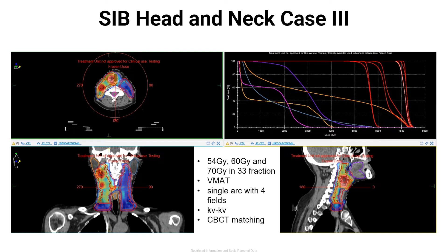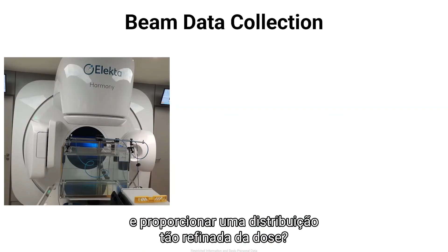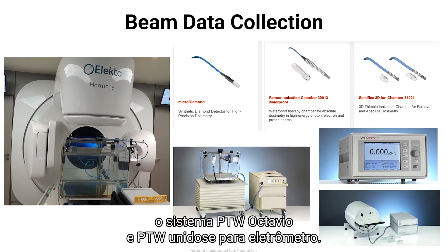So finally, let me give you the technical evaluation of the machine, and how this system can treat patients very successfully and give you a very elegant dose distribution. First of all, it starts with beam data collection. We perform beam data collection with our PTW equipment. We use a microDiamond for relative measurements. We use a Farmer ionization chamber for absolute measurements, and we use the MP3 system. For end-to-end tests, we use the PTW Octavius system, and we use PTW UNIDOS for electrometer measurements.